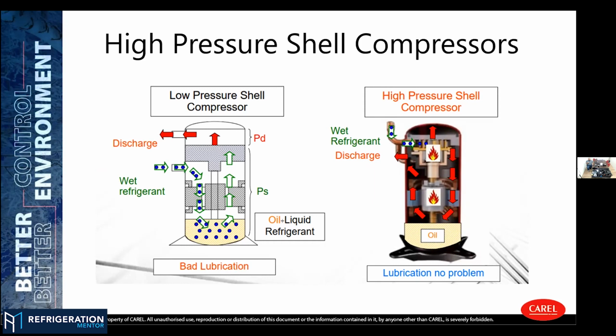Then the refrigerant goes into the compressor shell. It hits the shell of the compressor, and this shell acts as a first oil separation. So if the refrigerant plus the oil hits the shell, the droplets will fall down, and the refrigerant will keep going inside the compressor. The discharge temperature of the refrigerant cools down the motors. As you can see, this is a motor that can operate at very high temperature. We cool down the motor with this discharge temperature, and then the refrigerant flows to the discharge, to the condenser, or to the gas cooler.